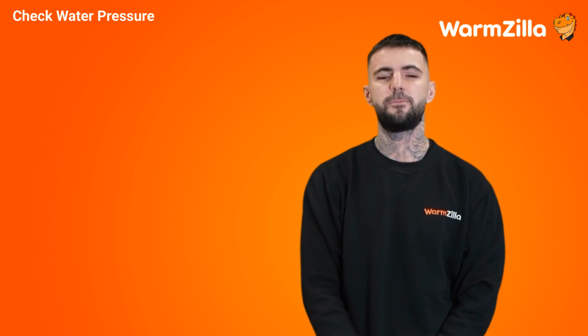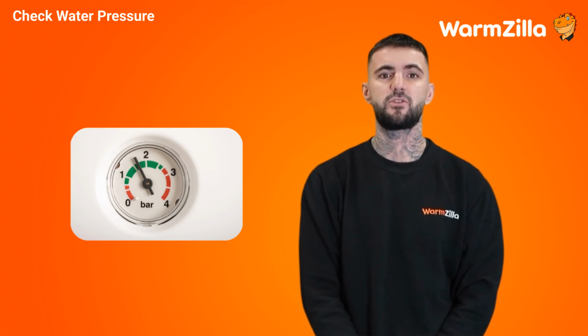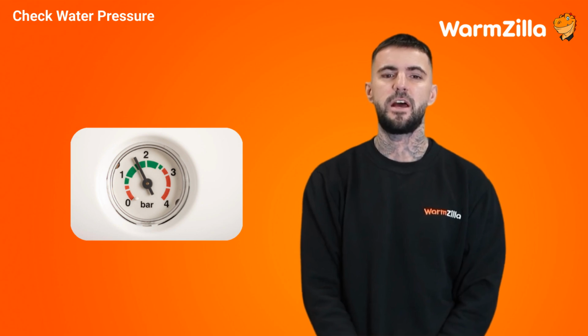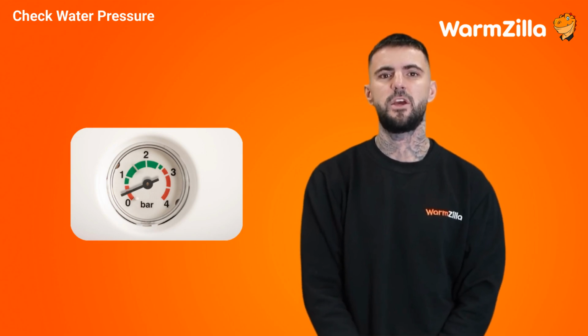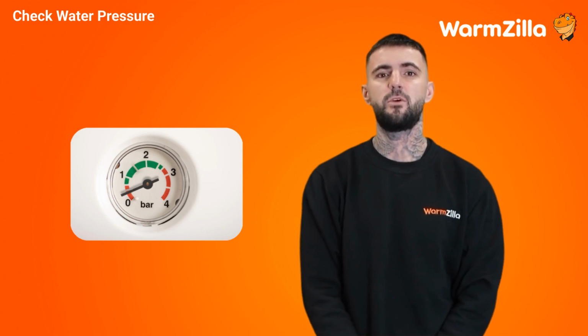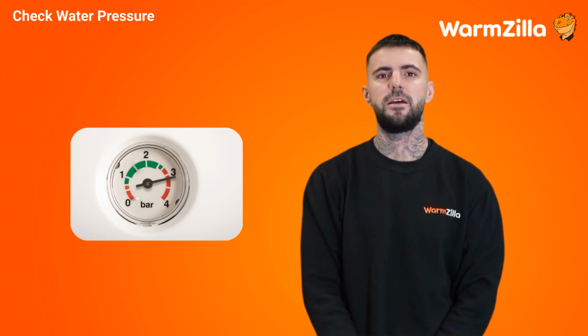Check water pressure. Most Combi boilers have a pressure gauge on the front panel, either as a dial or analog gauge, a digital screen, or, on older models, a physical gauge located under the unit. The reading should be between 1.0 and 1.5 bars when the system is cold. If the water pressure reading is below 1.0 bar, your boiler might need to be repressurized. On the other hand, if your Combi boiler's reading is too high, above 2.5 bars, you will want to bleed a radiator in your home to lower the pressure.